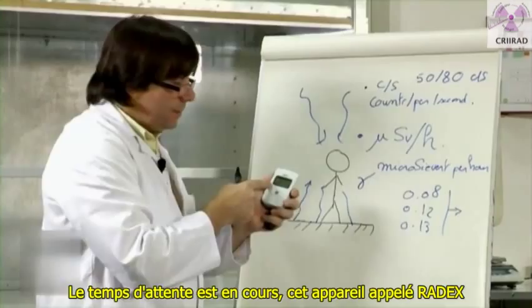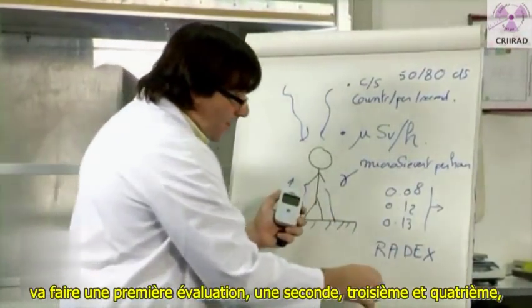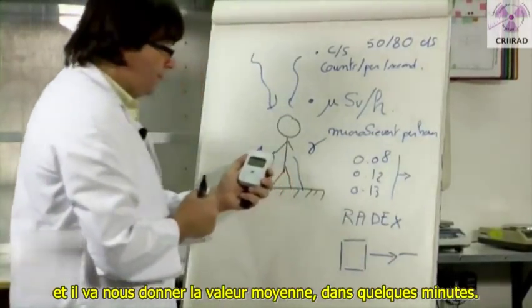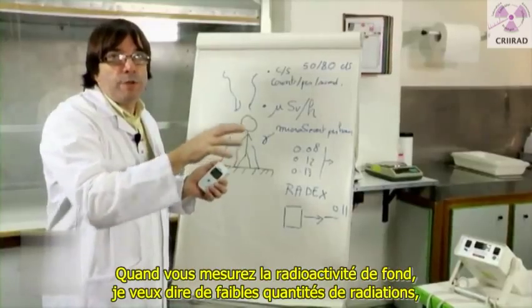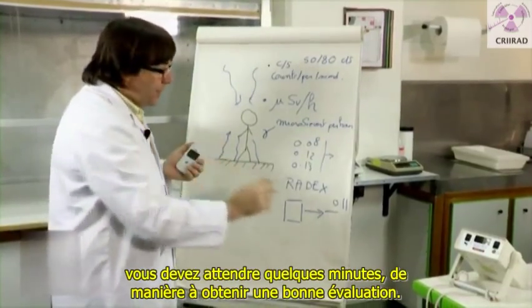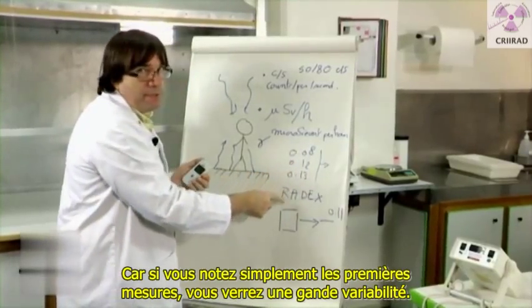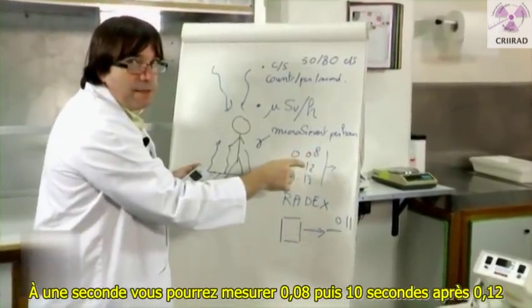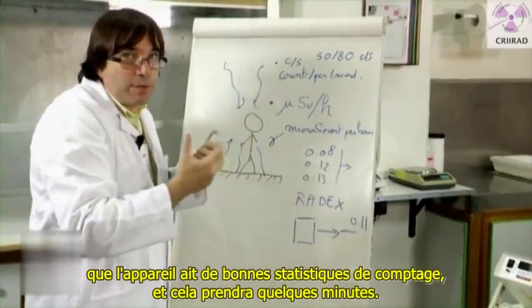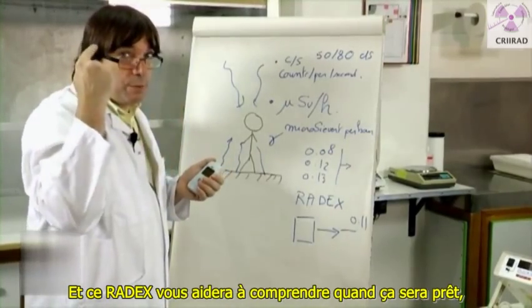The way it works is that this device, called RADEX, will make a first evaluation, second, third, and fourth, and it will give us the mean value in a few minutes. When you measure background radiation — small amounts of radiation — you have to wait a few minutes to get a good evaluation. Because if you just write down the first measurements, you see big variability: at one second you may measure 0.08, then 10 seconds after 0.12, and maybe 0.05, etc. So you have to wait for the device to have good counting statistics, and this RADEX will help you understand when it is ready — when it has finished the symbol on the screen.